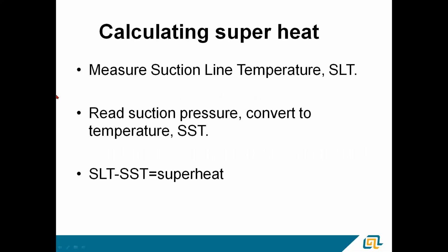So to calculate superheat, measure the suction line temperature, SLT. You read your suction pressure and convert that to temperature, and that's your saturated suction temperature, or your SST. So if you take your suction line temperature, you subtract your saturated suction temperature, that's how you get your superheat.